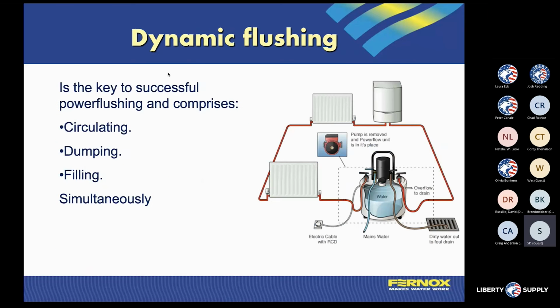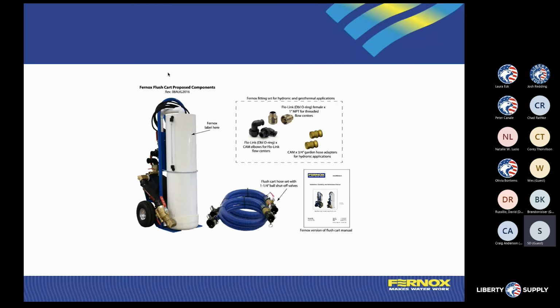We do have a pump system, so if you want to force that fluid through or flush the system out once that circulation process has been done, you can do it that way, or you can just do it in a standard drain and power bring in additional fluid to flush that system out as well. This is what our flush cart looks like. So that can give you not only the forward flow, connect yourself to a water supply, connect yourself to a drain off point. So when you drain the system, you go right into a floor drain or remove the fluid out of that system.